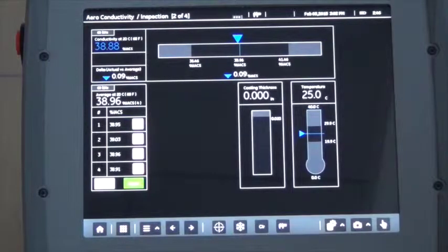The inspection procedures in this area vary. One manufacturer calls for a minimum of 4 points. Another manufacturer just says take several. You can set a threshold for that when you design the workflow. In this case, I've made it the requirement that we take at least 4 points for the average.